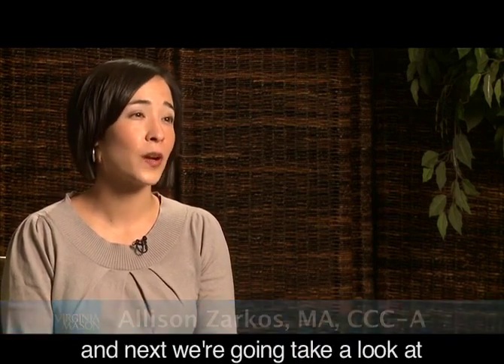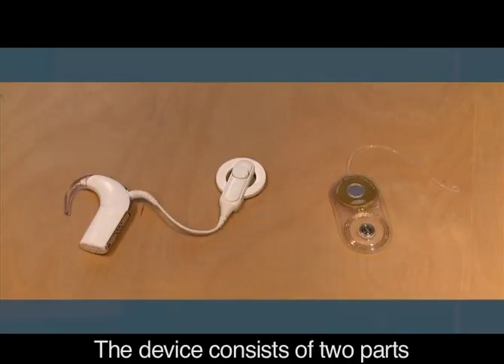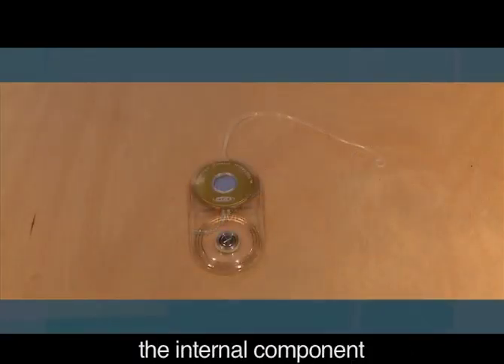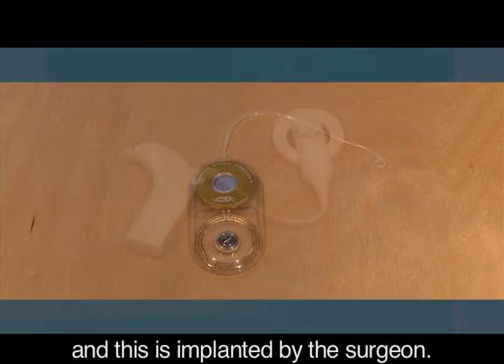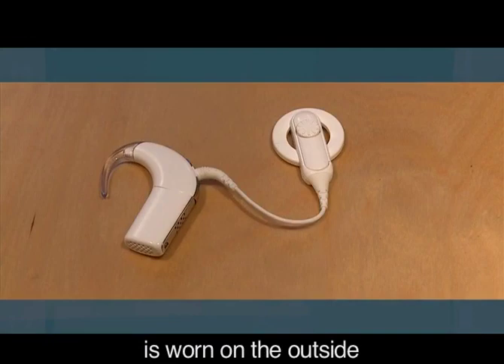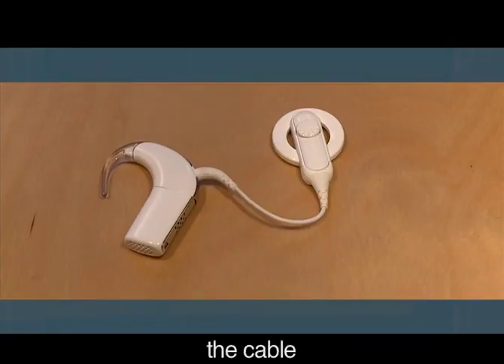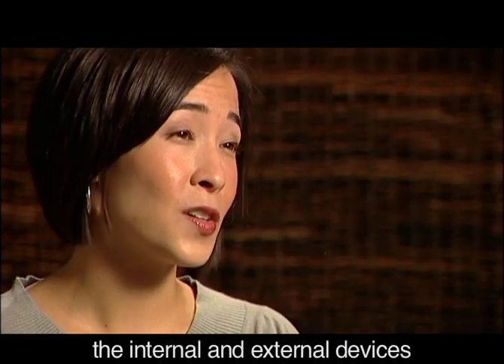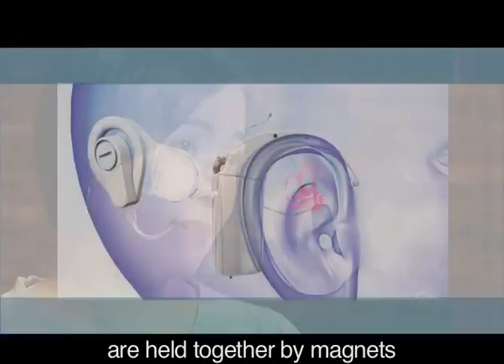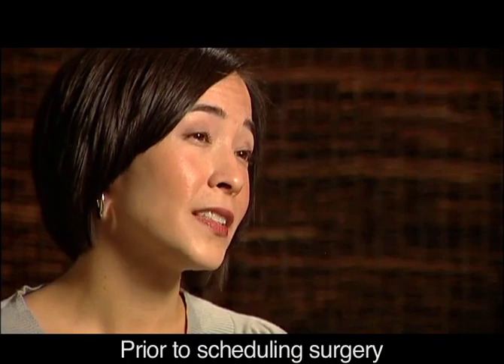I'm Allison Zarkos, another audiologist at the Listen for Life Center, and next we're going to take a look at the actual cochlear implant device. The device consists of two parts. The internal component has a receiver stimulator and an electrode array, and this is implanted by the surgeon. The external device is worn on the outside, typically over your ear. It's composed of the processor, the cable, the coil, and a power source. After implantation, the internal and external devices are held together by magnets and they communicate by radio waves.